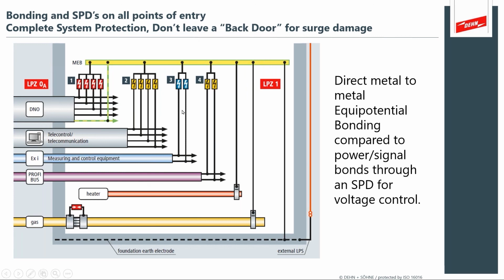But now look what you've got. You've got surge protection devices that are bonding to your electrical equipment. So your main electrical power, your telecommunications, your low voltage data systems, and your other important data control systems are connected through the SPD to provide voltage control. That's what an SPD does. It essentially bonds during the lightning event, during the surge event, and provides control of voltage and gives the surge current a path into the main earthing bar and then into the soil.